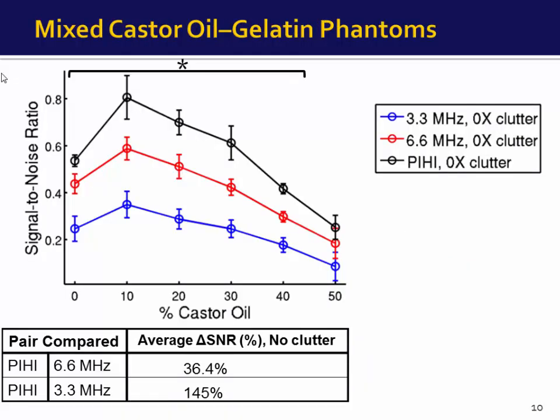Shown here is SNR on the y-axis versus castor oil percentage. In blue is the 3.3 MHz TSI data, in red the 6.6 MHz data, and in black the pulse inversion data. For castor oil percentages from 0 to 40 percent, the SNR for pulse inversion tracking was better than fundamental tracking — 36.4 percent improvement compared to 6.6 MHz and 145 percent improvement compared to 3.3 MHz.